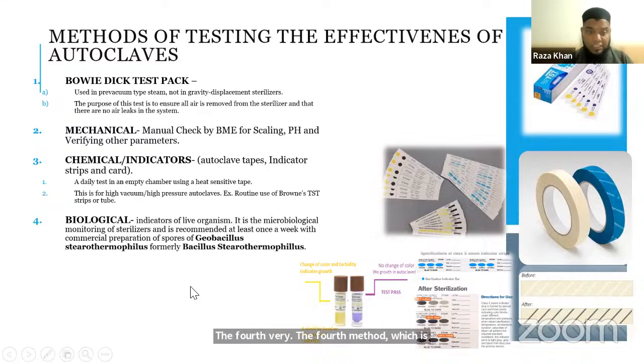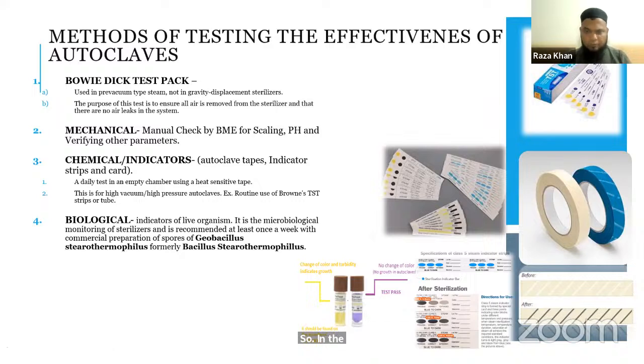The fourth method, which is very essential, is the biological test or biological indicator method. It helps us to check the efficacy of autoclave. For this, we use spores like Geobacillus, formerly Bacillus, and put them in the autoclave, and then we grow them. A few years ago, we used to grow the culture in a lab or incubator, but nowadays we are using vials, which with the help of color change indicate whether spores have grown or not. In the picture, you can see the yellow and the purple tubes used for biological indicators.